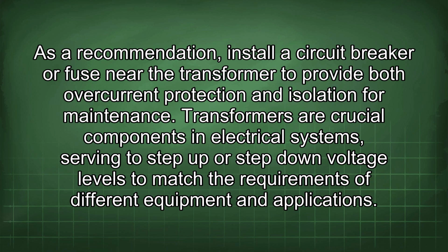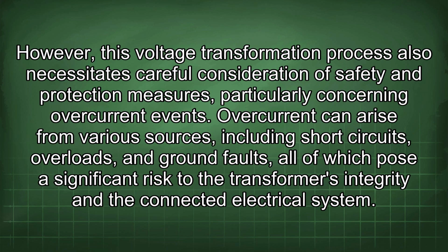As a recommendation, install a circuit breaker or fuse near the transformer to provide both overcurrent protection and isolation for maintenance. Transformers are crucial components in electrical systems, serving to step up or step down voltage levels to match the requirements of different equipment and applications. However, this voltage transformation process also necessitates careful consideration of safety and protection measures, particularly concerning overcurrent events.